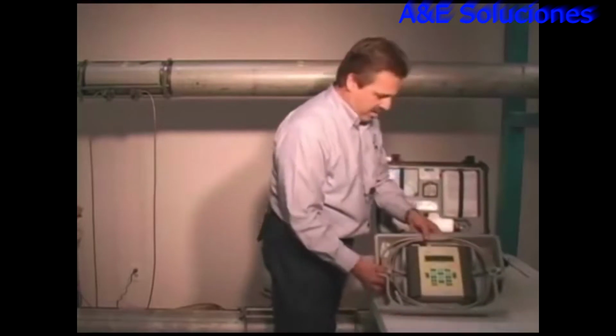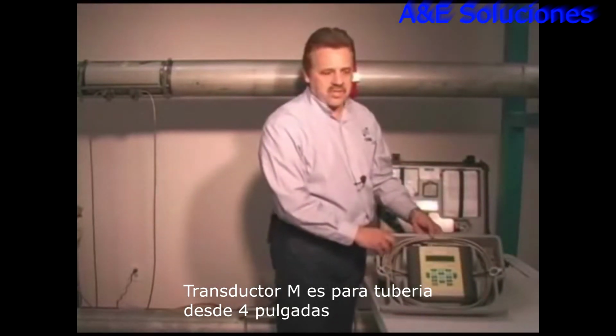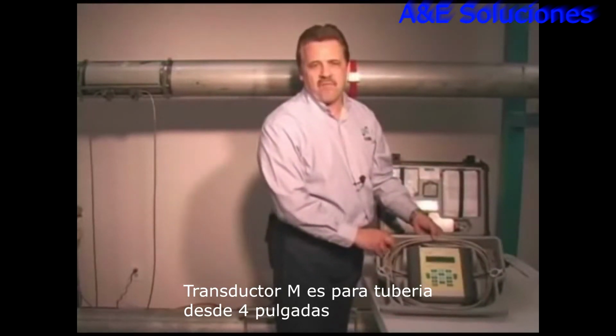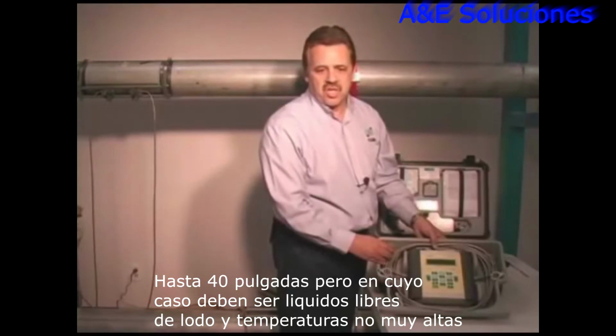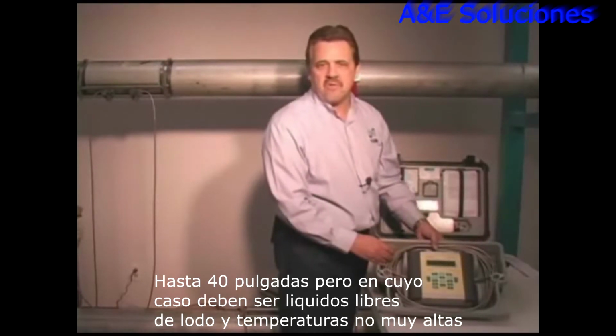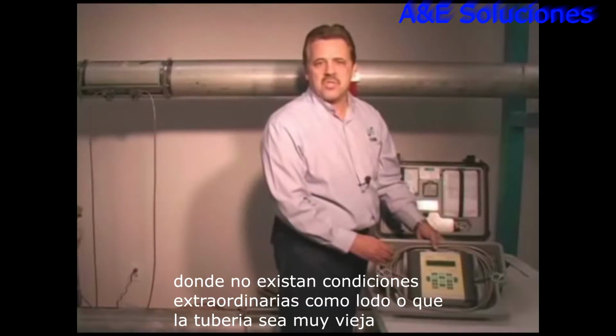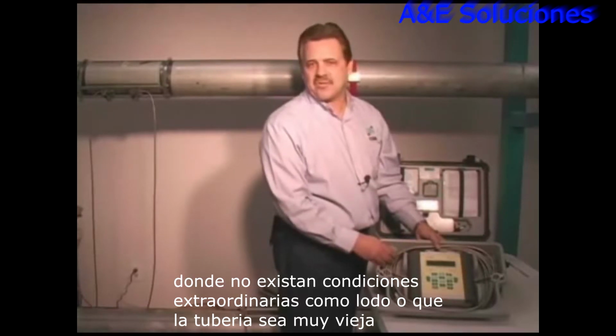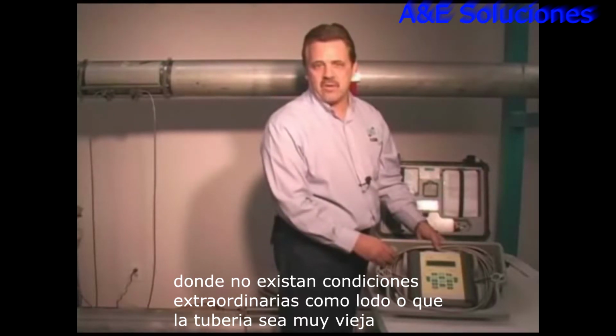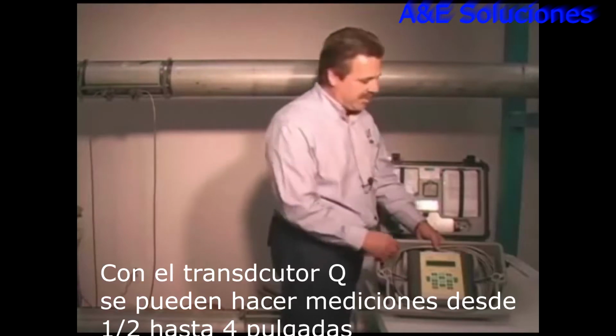With the M size transducer, you can cover from roughly 4-inch pipes to essentially the largest size pipe that you can still get a signal through, which depends somewhat on the pipe conditions, but you can easily do a 40-inch pipe, a chill water type application, or most liquid applications that are not introducing an extra level of challenge like a slurry or old pipes that may have a lot of scaling buildup.